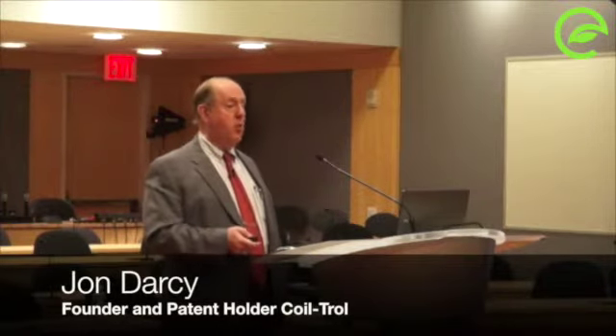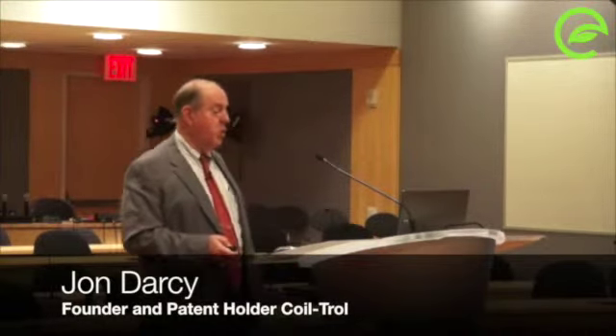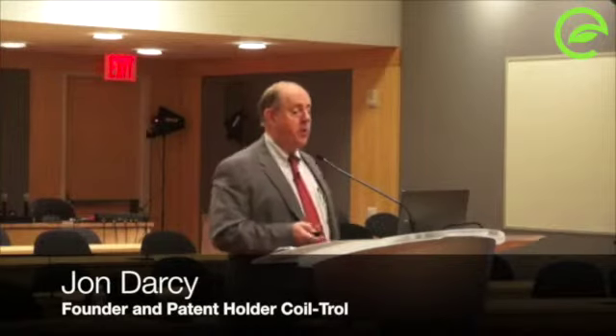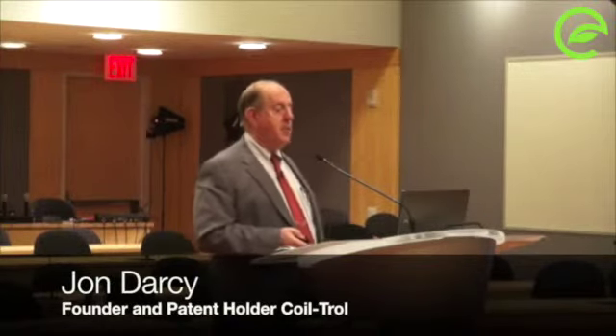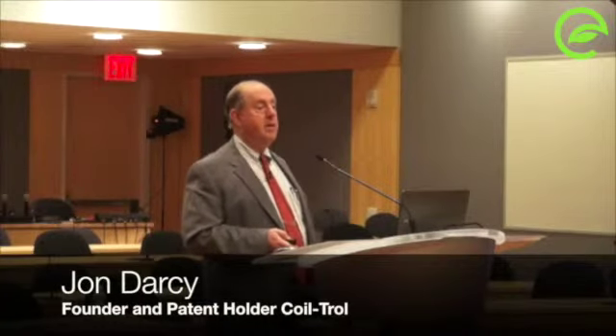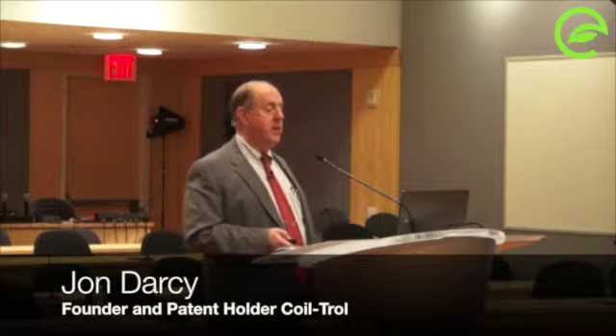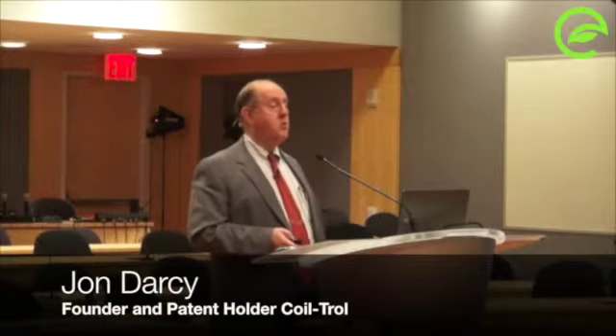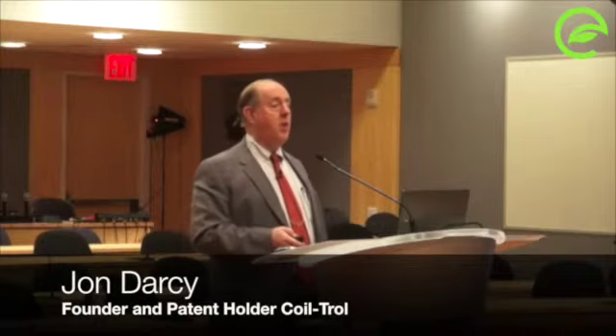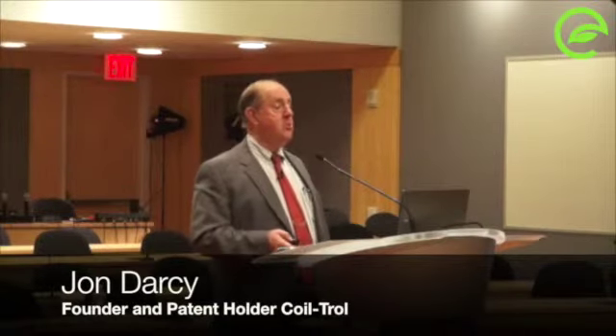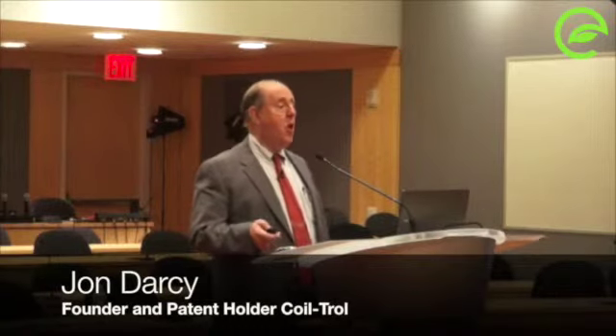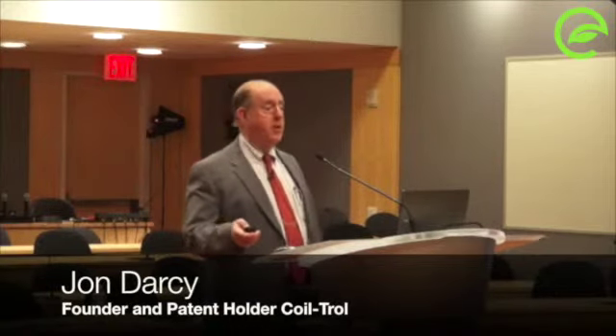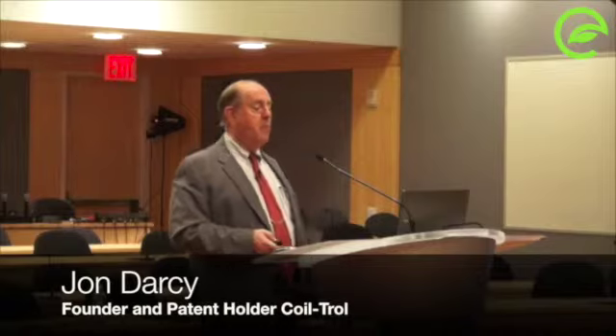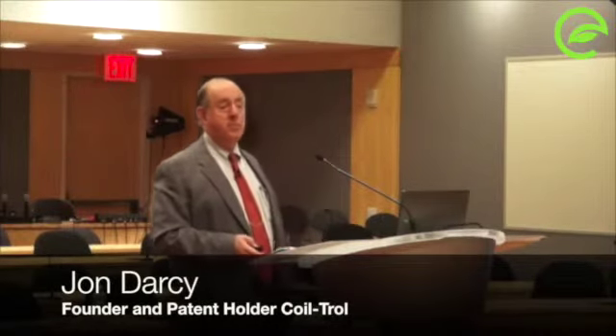I learned a whole lot more about the coils, where we're really delivering the cooling. So the Coil-Trol is a process where we reduce the excess cooling in the coil, and most of that excess cooling is done either as sensible, because we're resetting the discharge air temperature coming off the coil, and as latent. And those numbers can be anywhere from 15 to 25%, depending on what temperatures you were operating your discharge air on your air handling units to start off with. We came up with a way of reducing the pumping costs by 20 to 40%.